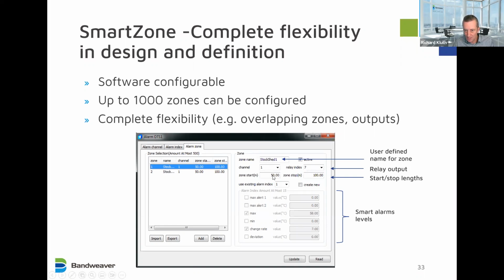where it starts, where it stops, and then the different levels: maximum alerts, pre-alerts, change rate, deviation, even minimum if you want, if you're going cold. That's more for leak detection than fire. And so a very simple interface for programming.